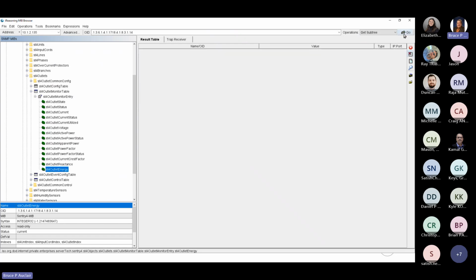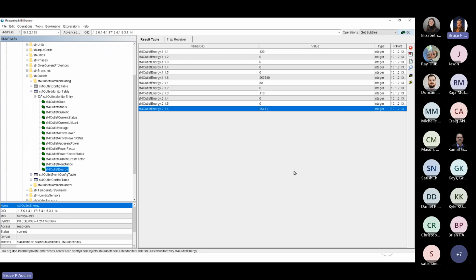Clear the tree. And in this case, these PDUs are not brand new. I have been using outlet number one only for a little bit, just powering this fan for a short while. But I have had other devices connected to other outlets for some time. And so we see an energy value. Energy is an accumulator. It's like an odometer in a vehicle. So it's an ever increasing number, which is why when using energy values, you need both a start reading and an end reading in order to determine consumption over a period.